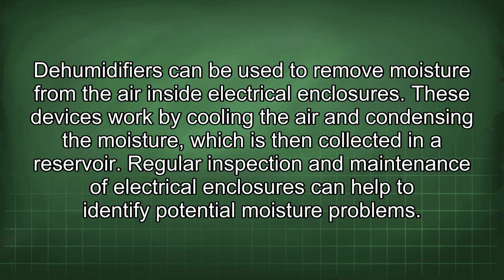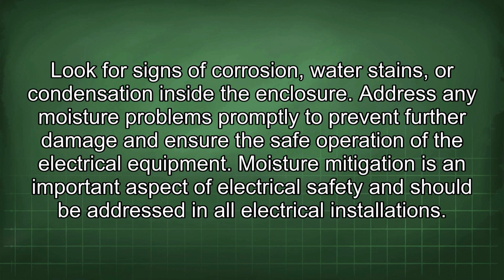Regular inspection and maintenance of electrical enclosures can help to identify potential moisture problems. Look for signs of corrosion, water stains, or condensation inside the enclosure. Address any moisture problems promptly to prevent further damage and ensure the safe operation of the electrical equipment.